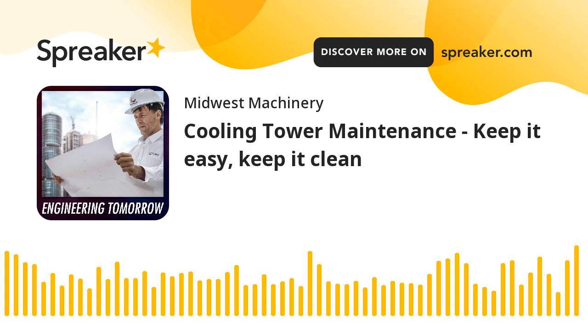Any sort of separator is definitely recommended with the cooling tower. You are going to get stuff in your tower. Even with the cottonwood screen, you're only going to be able to keep out so much, so some of that you need to expel before it reaches your other equipment that could be damaged. By paying a little bit up front, you can protect all of your equipment, especially chillers, which are wildly expensive. Putting in a separator to get rid of some of that dirt and debris before it gets there can really save the life of your chiller.